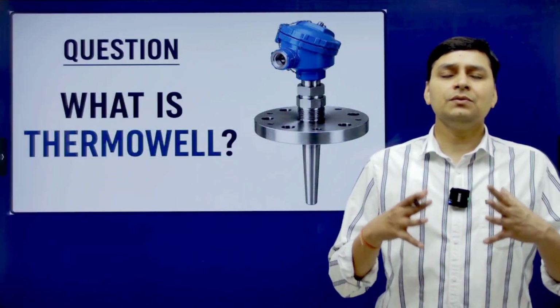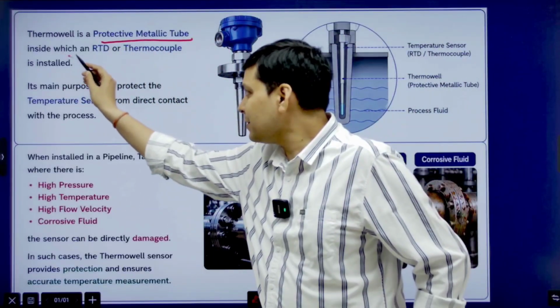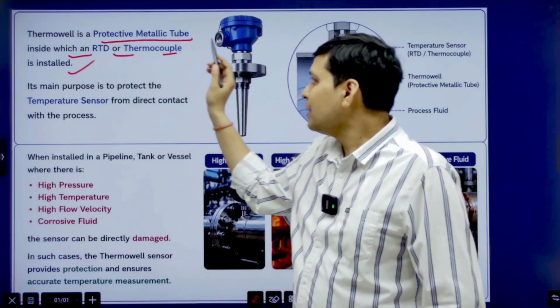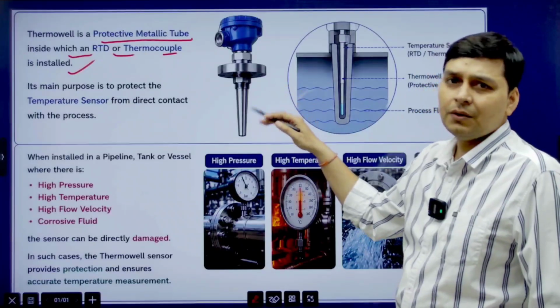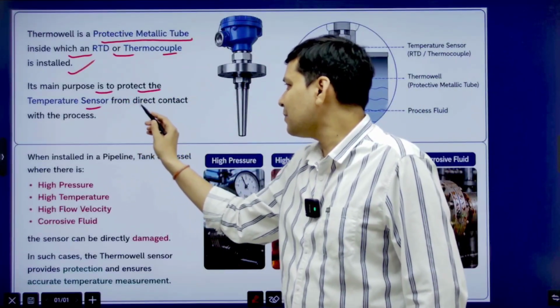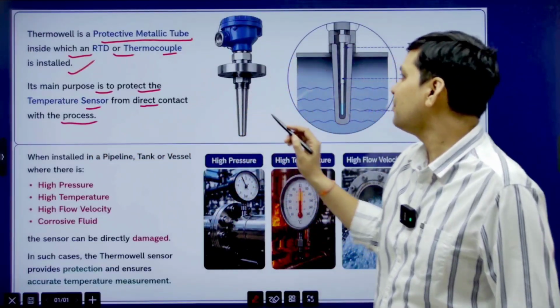Another important question, what is Thermowell? Look friends, Thermowell is a protective metallic tube inside which an RTD or thermocouple is installed. We use Thermowell with RTD or thermocouple. Its main purpose is to protect the temperature sensor from direct contact with the process.